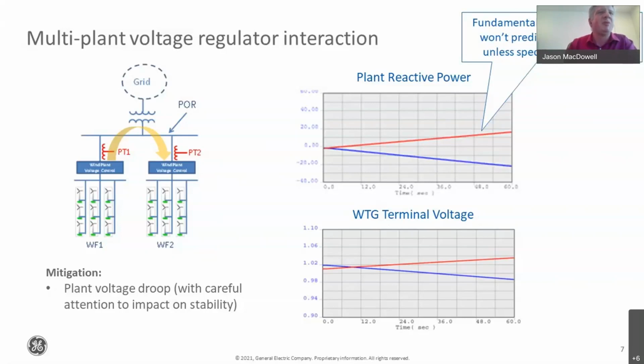Voltage droop is one of the ways to coordinate this and mitigate it, but without asking the question, what is out in the grid? Are there multiple plants around near me in my interconnection? Do I need to evaluate this control interaction at the plant level, and do I need voltage droop? That question should be asked right up front, very early on.